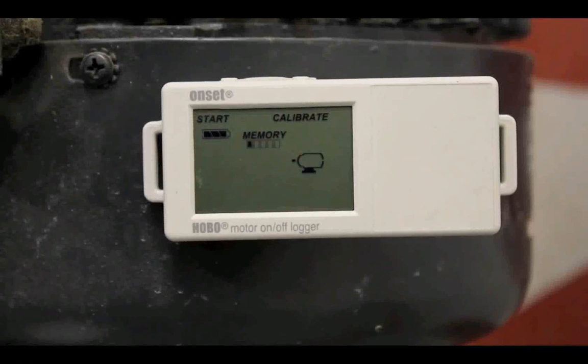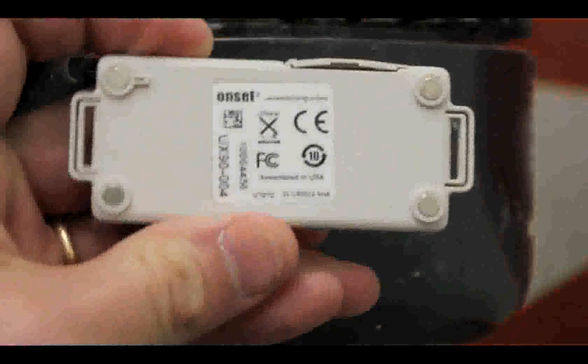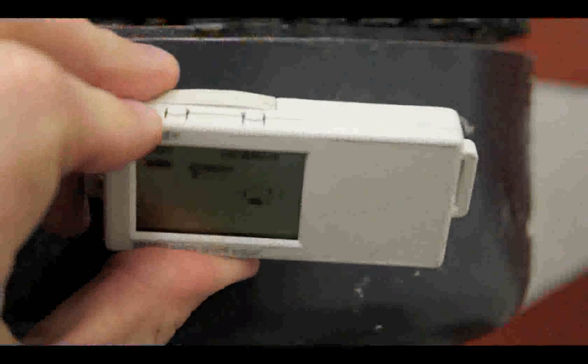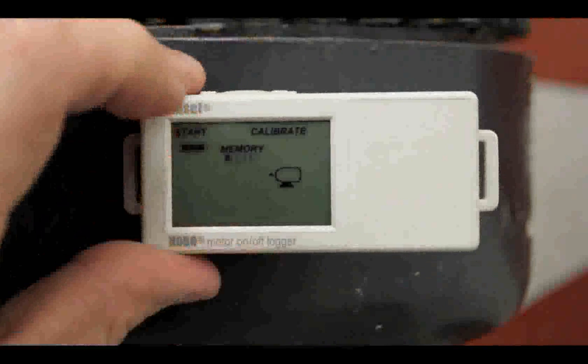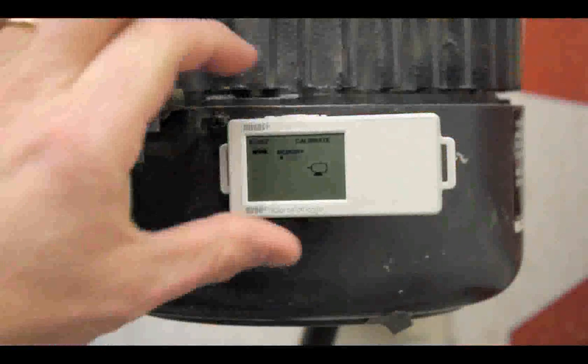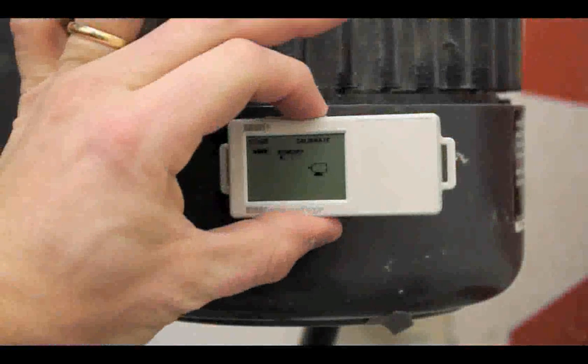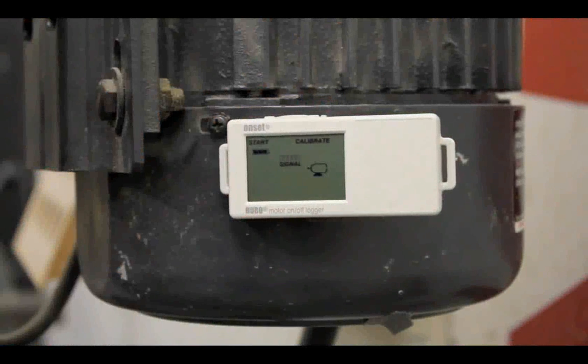This is Onset's new redesigned motor on-off logger, part number UX90-004. This video will demonstrate the new signal strength, auto calibrate, and start and stop features. The motor on-off logger is connected to a 2 horsepower drill press by the 4 rare earth magnets that we have on the back of the logger. On the top, we have 2 buttons. The right push button is for the calibrate and signal strength, where the left button is for the start and stop feature. By pushing the button on the right hand side, you're going to be able to change from memory over to signal strength. As you can see, there are 0 bars at this point.